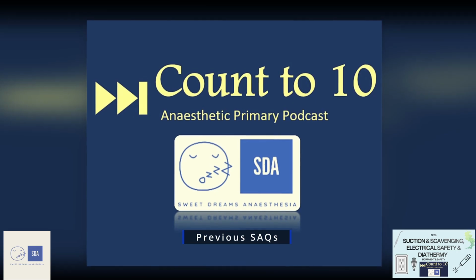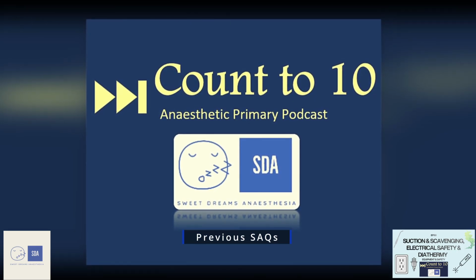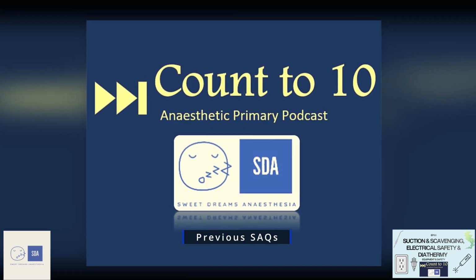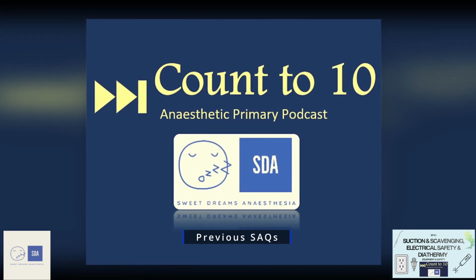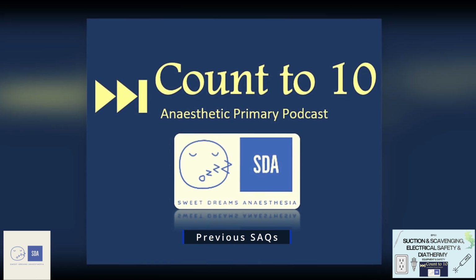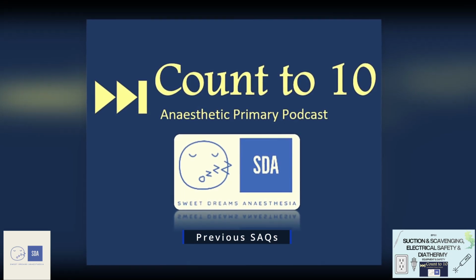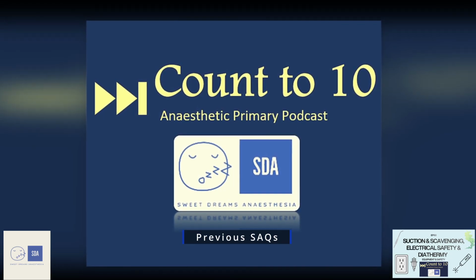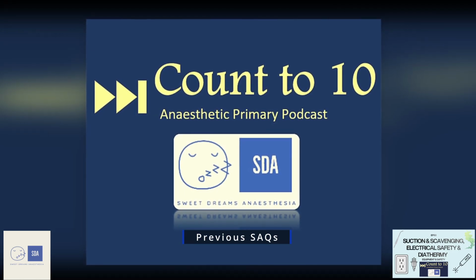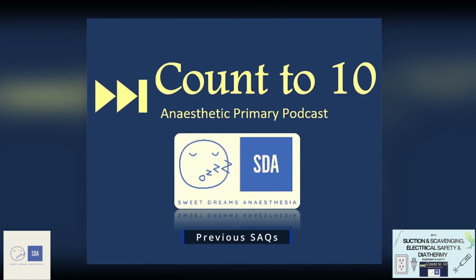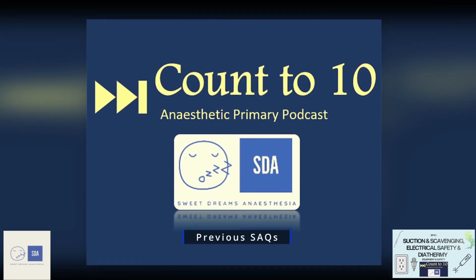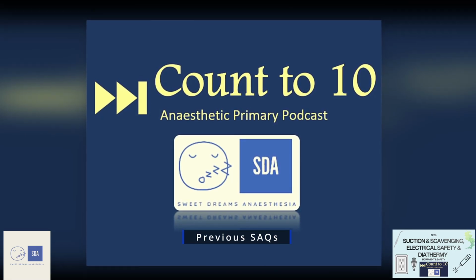Fresh gas is being added continually to the circle breathing system, and this must have a means to escape. This is one of the functions of the APL valves. Scavenging is coupled to these to collect the waste gases, to prevent pollution to the operating theatre. The other good area to recognize is that scavenging systems are designed such that suction cannot be applied directly to the breathing system, and that's why they have those open apertures to entrain air. This is why the reservoir chamber is required, because it's distal to the point of collecting and transferring those gases.